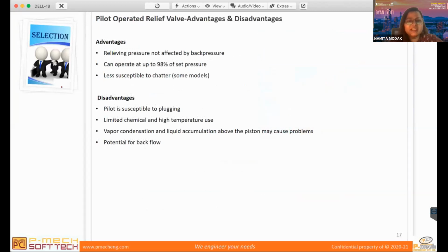The advantages are that the relieving pressure is not affected by back pressure, it can operate up to 98% of set pressure, and it is less susceptible to chatter. The disadvantages are that the pilot is susceptible to plugging, it has limited chemical and high temperature use, vapor condensation and liquid accumulation above the piston may cause problems, and there is potential for backflow. So these are the advantages and disadvantages of the pilot operated valve.